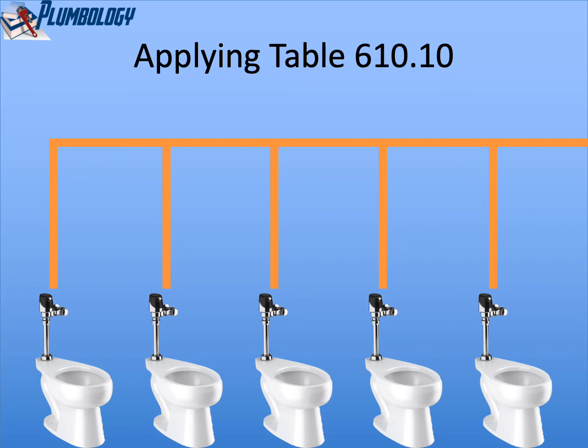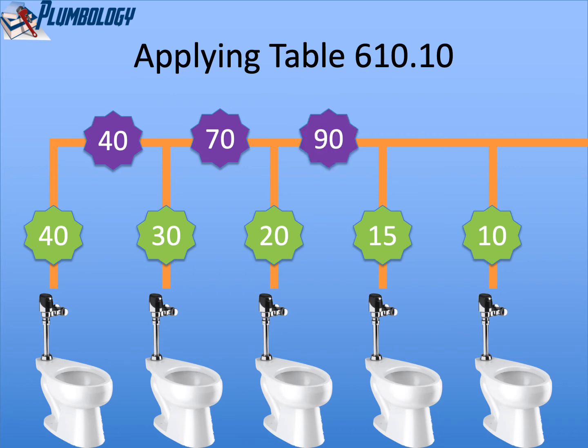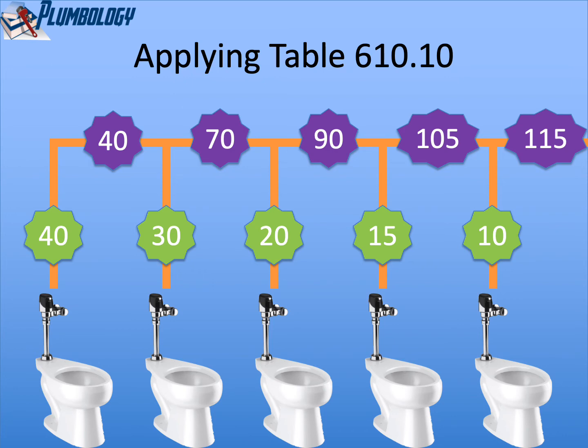Finally, if we have five water closet flush valves, we still use the same decreasing scale starting with 40, then 30, 20, 15, 10. Going back to do the pipe segments: 40 plus 30 gives us 70, plus 20 gives 90, plus 15 puts us at 105, plus the last one which is 10 gives us 115. So that water pipe branch would be sized for 115 water supply fixture units.